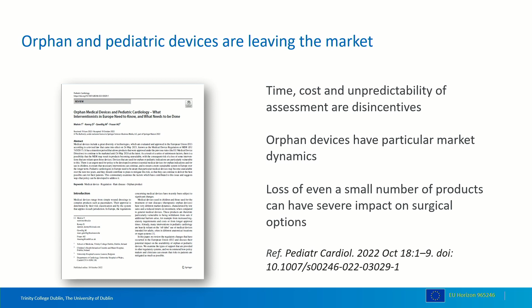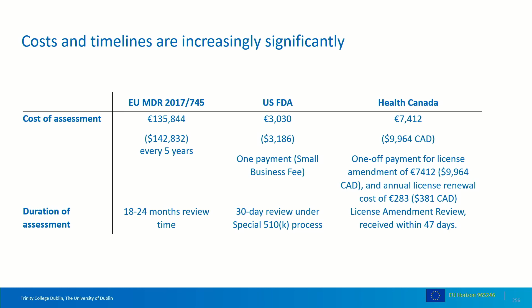So you can see for the medical device regulation for that Rashkind balloon catheter, the quote they got was €135,000 and it will take 18 to 24 months. And for that reason, that product may be lost from the market. It follows a 510(k) pathway in the United States, but you can see the cost there is €3,000, and that's for lifetime marketing for the product, whereas in Europe it has to be updated every 5 years.